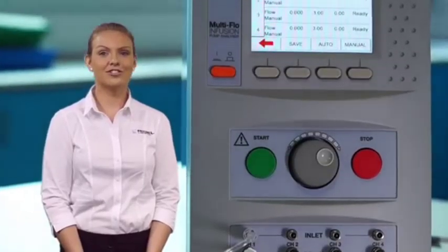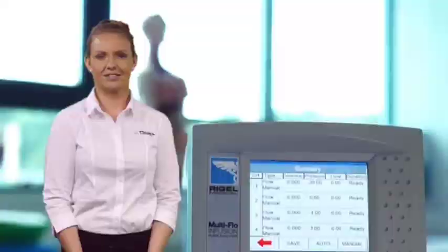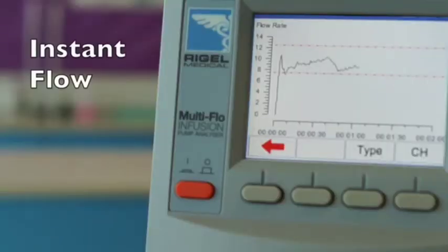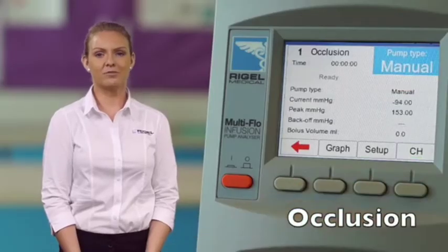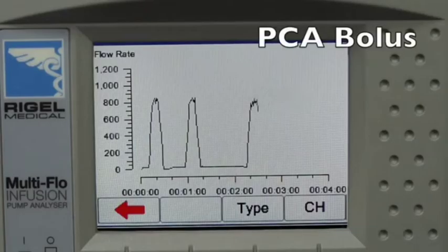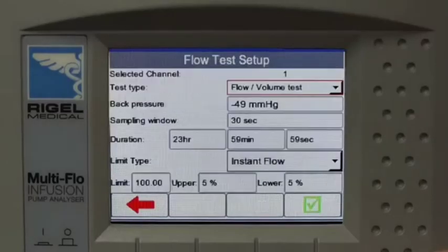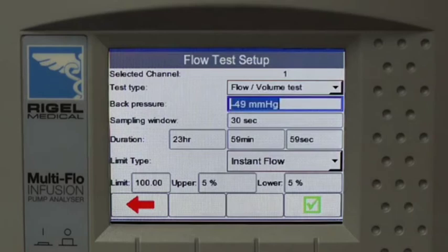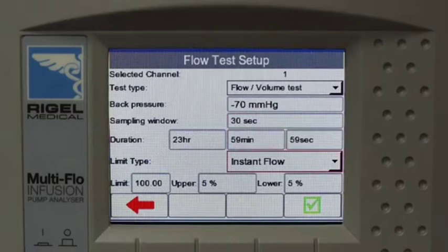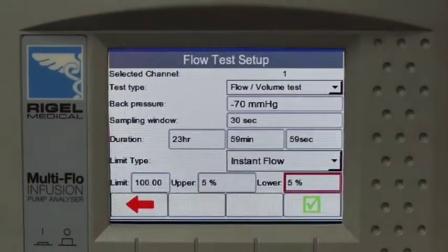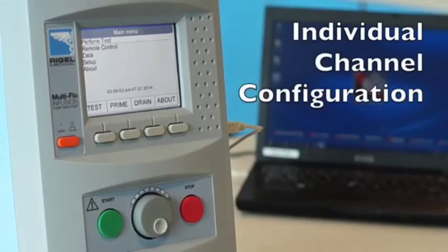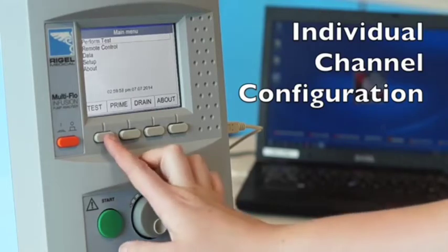It's a single or multi-channel infusion pump analyzer. It provides accurate instant flow measurements from 10 microliters per hour up to 1,500 milliliters per hour, occlusion pressure measurements, and PCA bolus measurements. The MultiFlow's internal pressure regulation can simulate a wide range of back pressures to meet the requirements of IEC 60601-2-24. The MultiFlow allows individual setups of each channel to run tests in either a manual or fully automatic configuration.